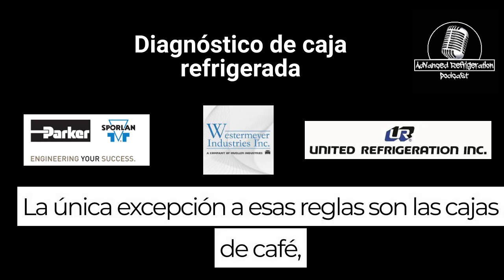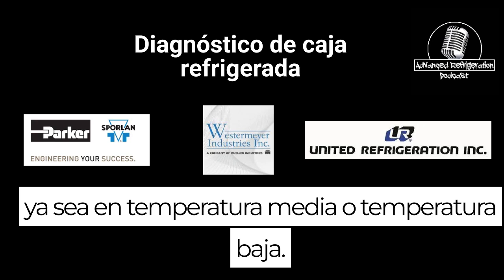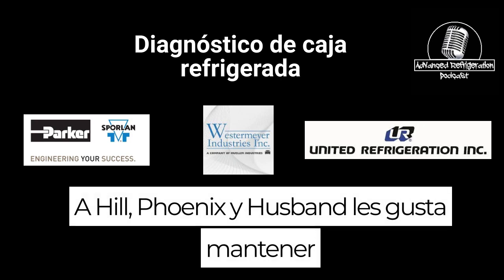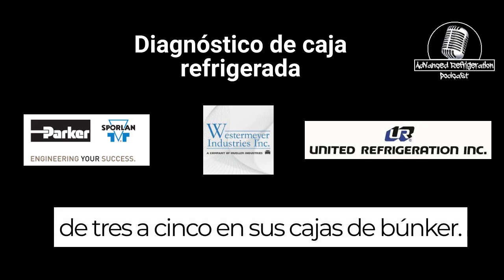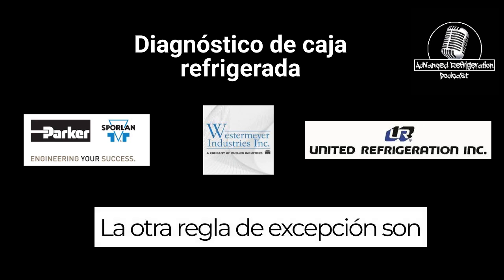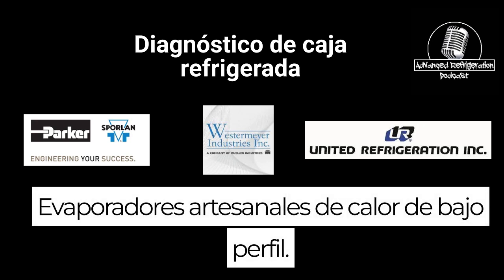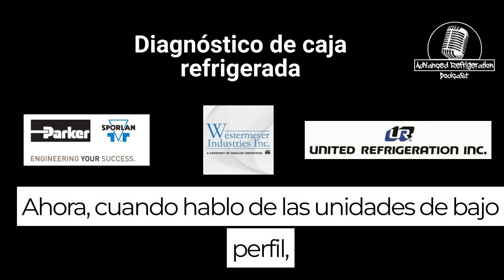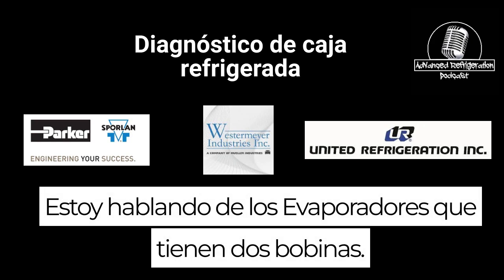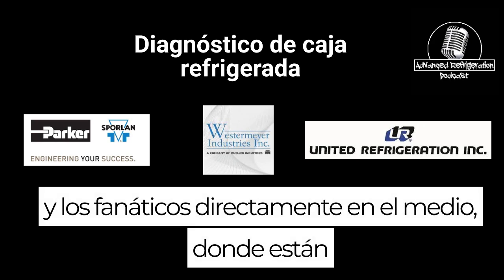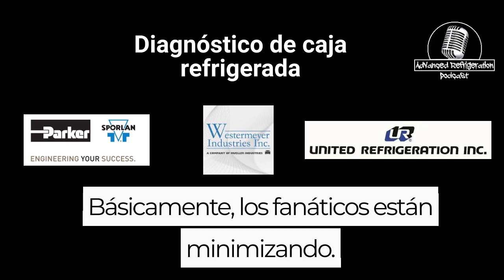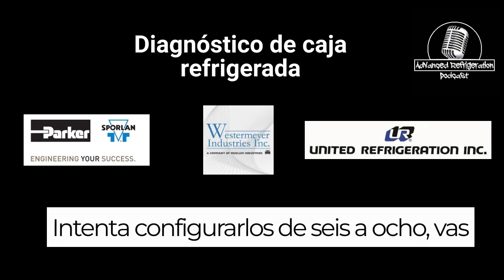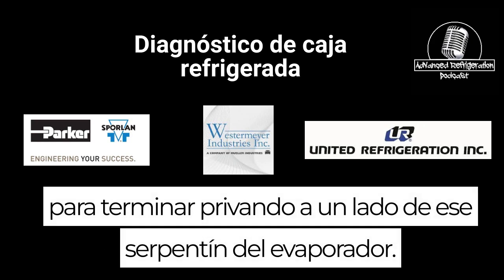The only exception to those rules are coffin cases, whether it's in medium temp or low temp. Hill Phoenix and Hussmann like to maintain 3 to 5 on their bunker cases. The other exception to the rule are low profile Heatcraft evaporators. When I talk about the low profile units, I'm talking about the evaporators that have 2 coils and the fans directly in the middle, where the fans are pointing down. If you try to set them for 6 to 8, you're going to end up starving out one side of that evaporator coil.